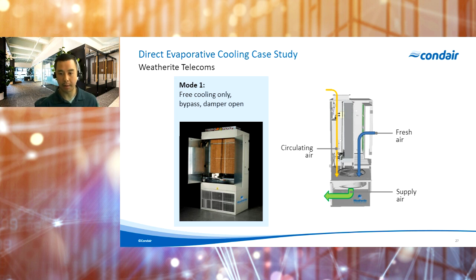So this system actually has two operating modes. Mode 1 is what we would call free cooling mode with the bypass damper open. How this works is at the top of the unit, we have the recirculating air damper. If that is open, we can recirculate air, mix that with fresh air from the outside and supply that to the space. If that recirculating air damper is closed, we can exhaust air as well. On the right side, we have the fresh air supply coming in. And then, as I mentioned, because this is a direct evaporative type system, there are filters installed on here as well. So when the cooling demand can be satisfied with recirculating air, fresh air, or a combination of the two, where they can mix in the supply air section and be supplied to the space, the system would be operating in mode 1.